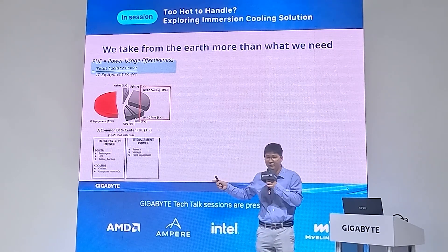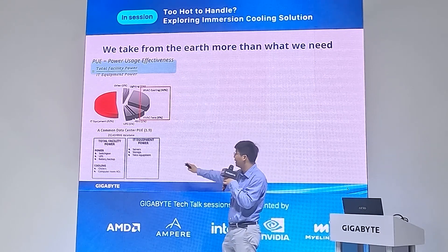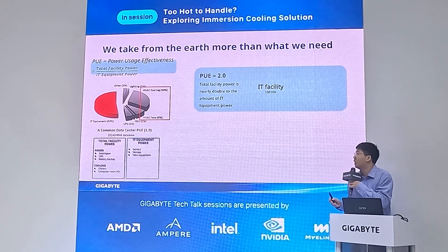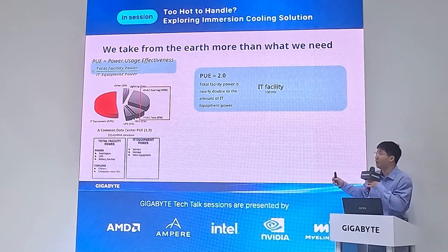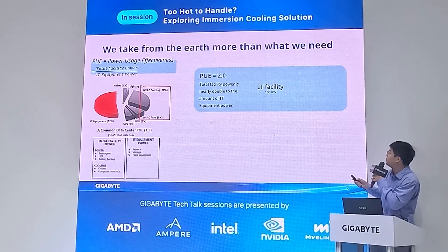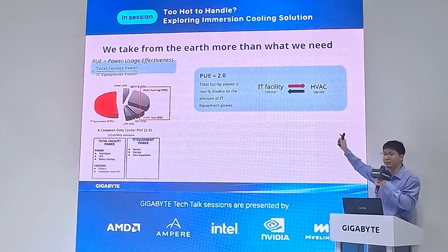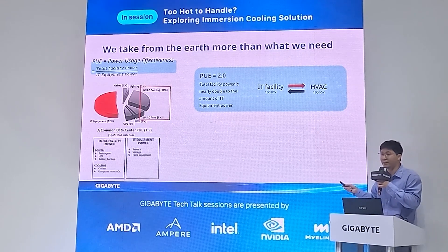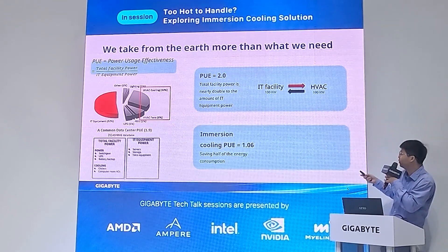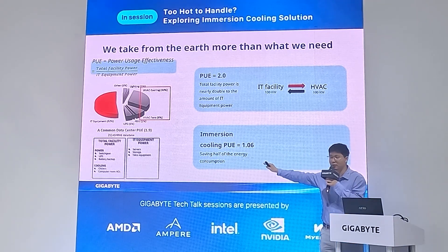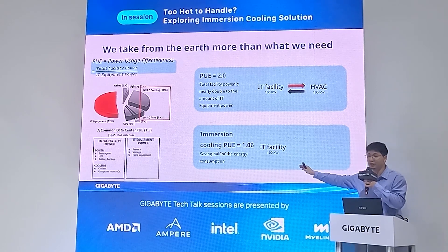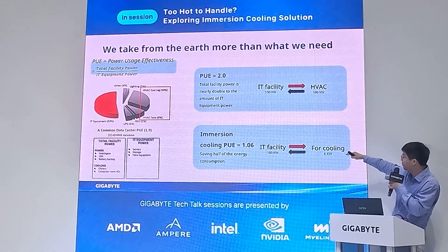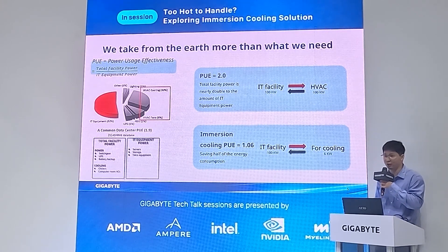For a common air cooling data center, PUE is 1.9 — from the ASHRAE database. If we use PUE 2.0 as an example, we generate 100 kilowatts for the server as IT facility, but we still need another 100 kilowatts for system cooling to offset the heat we produce — effectively doubling our draw on the earth. Whereas with immersion cooling, PUE is 1.06. We still generate 100 kilowatts for the server, but only need 6 kilowatts for system cooling — a huge energy saving.